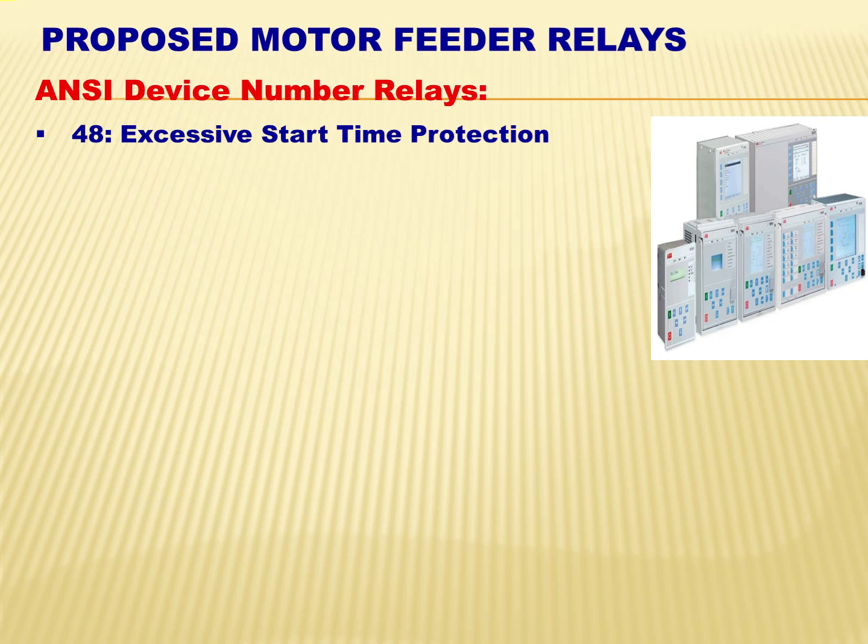So this relay 48 will be our second line of defense on overload protection. In particular, rotor critical high voltage motors can quickly be heated above their thermal limits when multiple starting attempts occur in a short period of time.